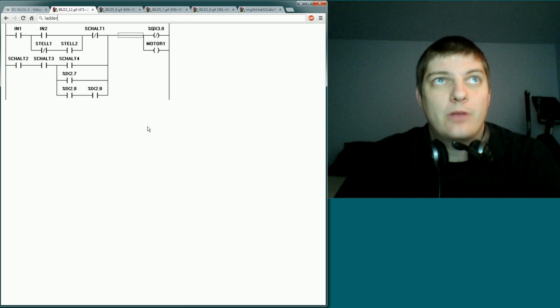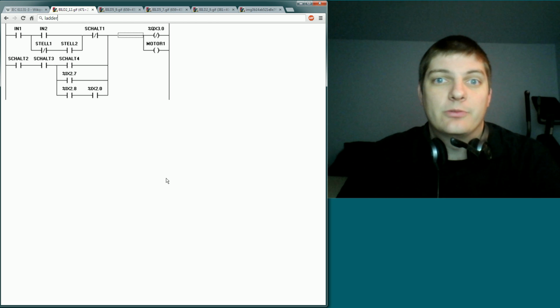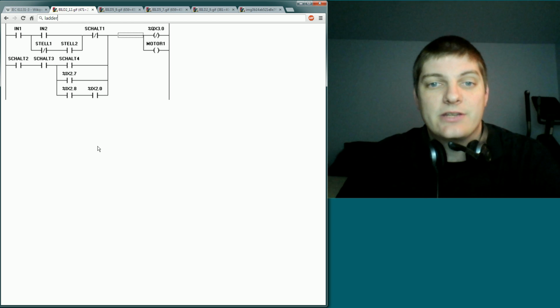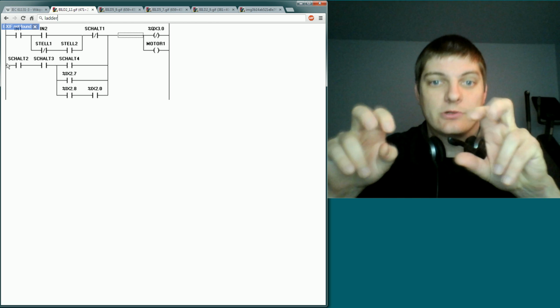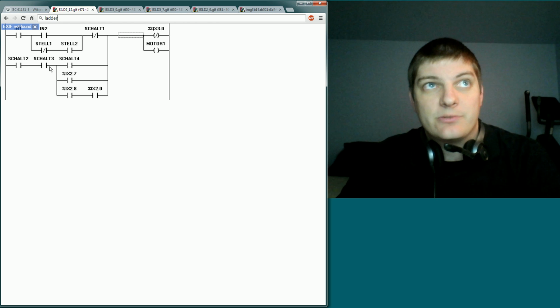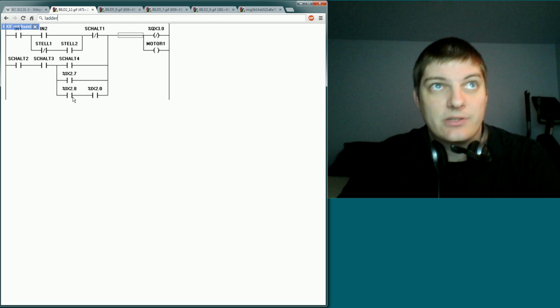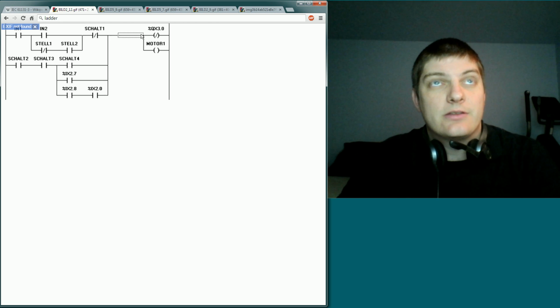This is going to probably be the most common. It's got the strongest foothold in the industry from my experience. A lot of the Rockwell programmers, especially the old school people, really love this stuff. I think it came from the old days of using relay diagrams or relay schematics. So you've got on the left side, here's where your power, quote-unquote, comes from. The right side would be your output. Any inputs along this way would be switches or some other sort of digital input. If they're in series, that's an AND. Once they branch out, that's an OR. And eventually they make it to the output side of the rung.